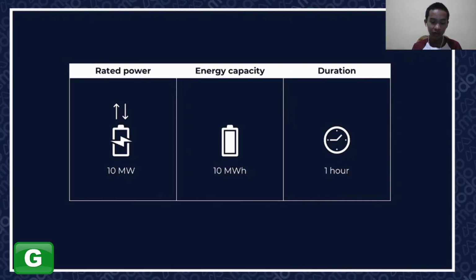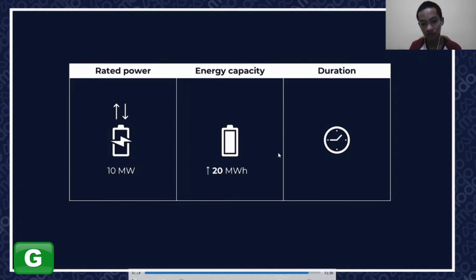To better understand rated power, energy capacity, and duration of a battery energy storage system: if a BESS has a rated power of 10 megawatts and an energy capacity of 10 megawatt-hours, it can have a maximum output of 10 megawatts for 1 hour to the community that needs it. When the energy capacity is 20 megawatt-hours, it can discharge a rated power of 10 megawatts for a duration of 2 hours. That's the gist of these three categories of a battery energy storage system.